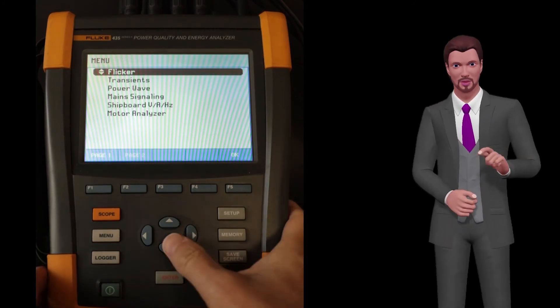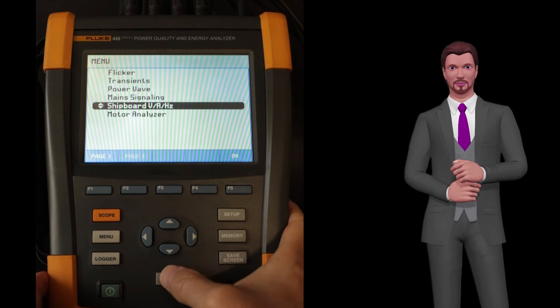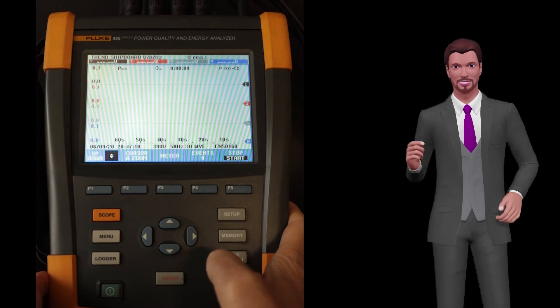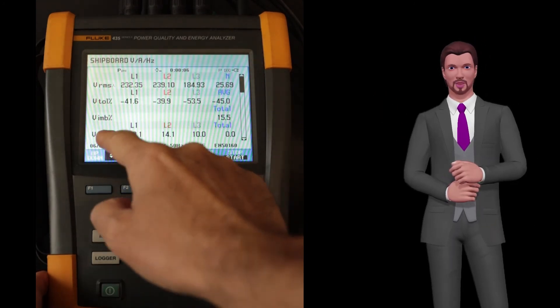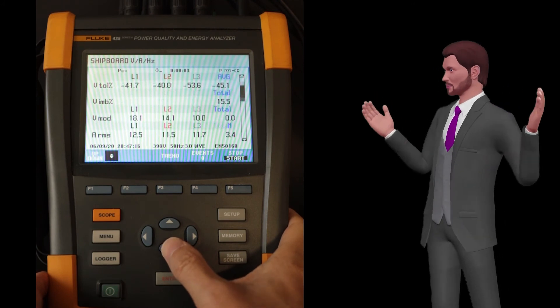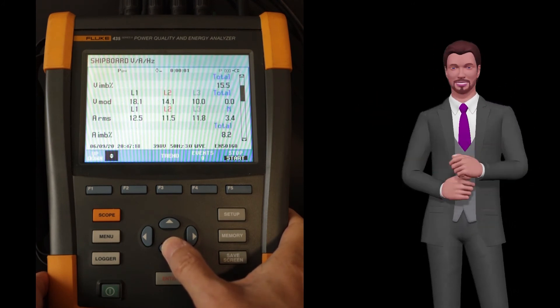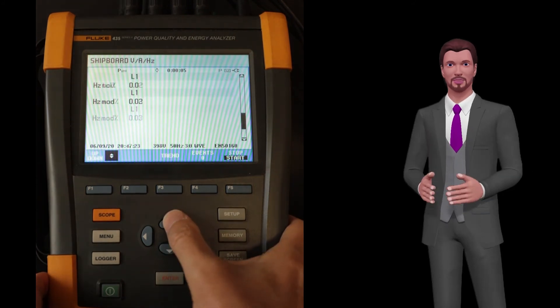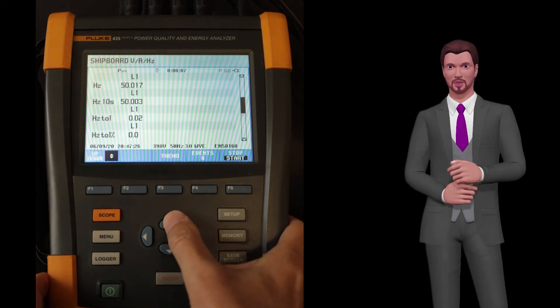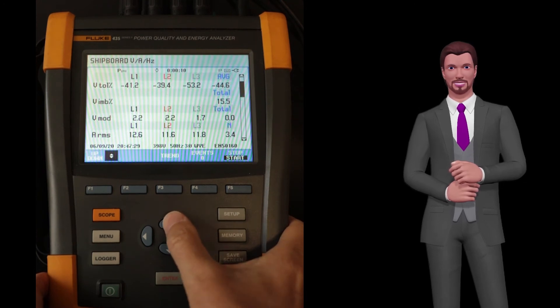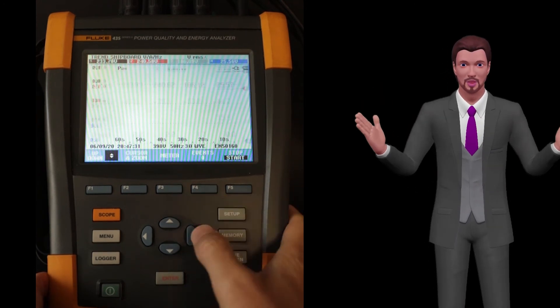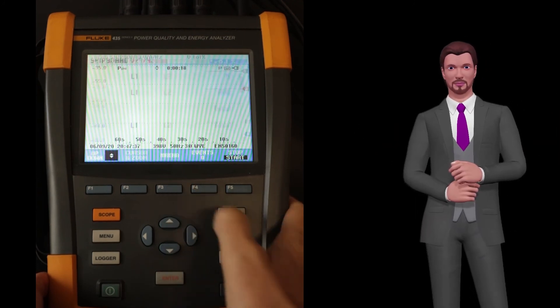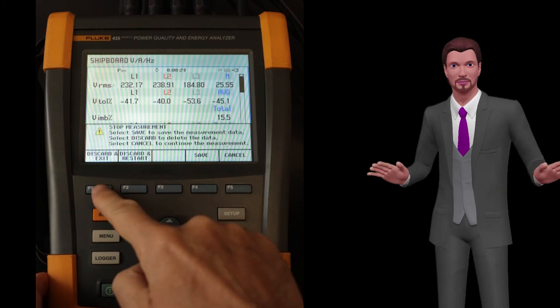The shipboard volts, amps, hertz function is present only in the 437 analyzer, and it is designed to carry out network analysis at 400 hertz, for example for power systems in ports and airports. Airplanes and different types of ships and submarines use electricity at 400 hertz in order to reduce the size of the power supplies. Normal analyzers only analyze networks at 50 or 60 hertz. In addition, for military ships there are power quality regulations that require special measurement parameters that the 437 has implemented through this function.